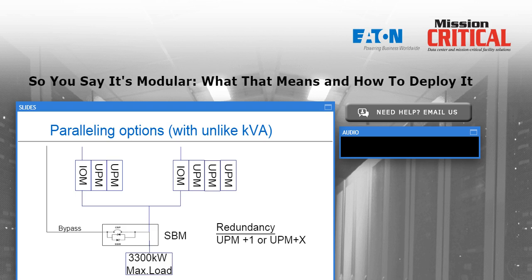Now, as time passes, they may need more capacity or they may want more redundancy. Do they have to roll in another one of these large UPSs? Not necessarily. Remember that each of these UPSs can add an additional UPM mounted on the left-hand end of the lineup. So they can bring in another 300 kilowatts of capacity at any time and install it in the field, or if they find that they're not redundant and they don't want to go get another large UPS and battery system, they can simply add an extra UPM on the left-hand end of either of those modules and retain that highly desirable N+1 redundancy.